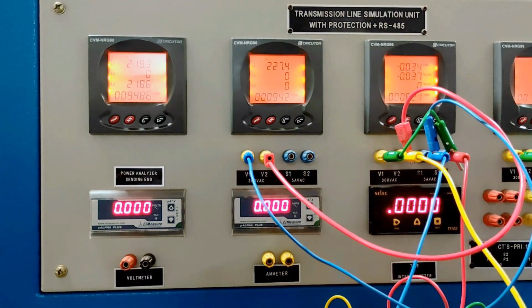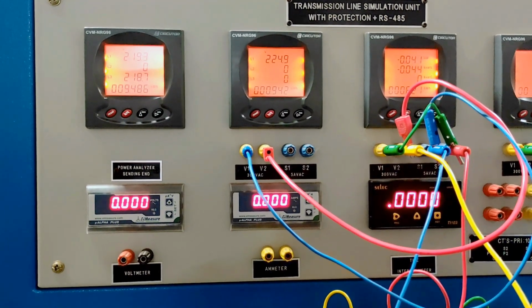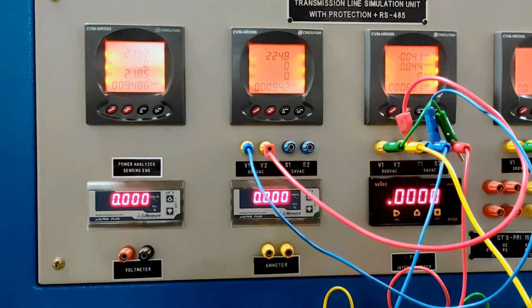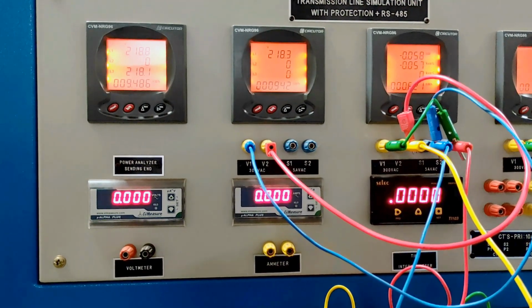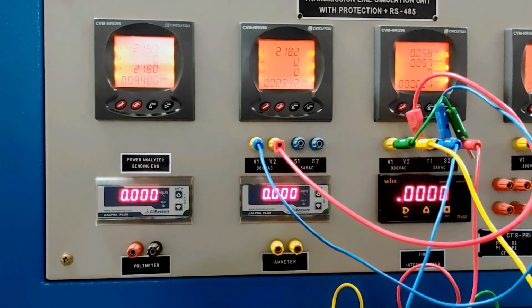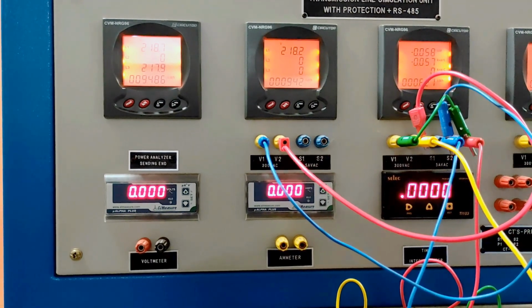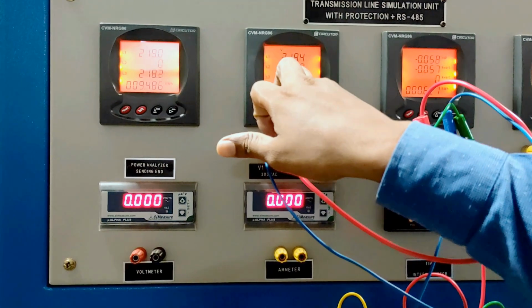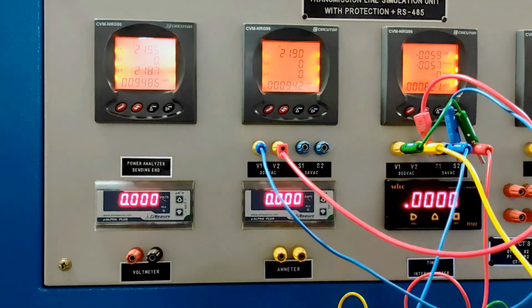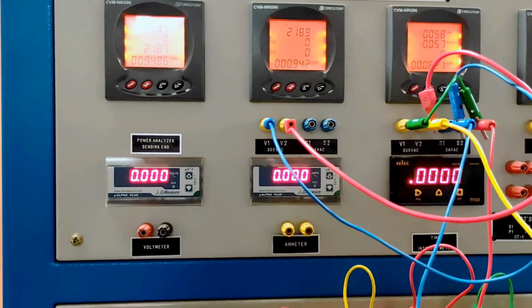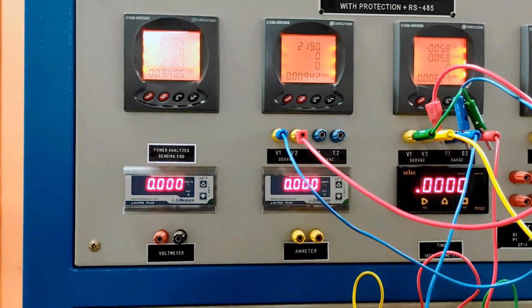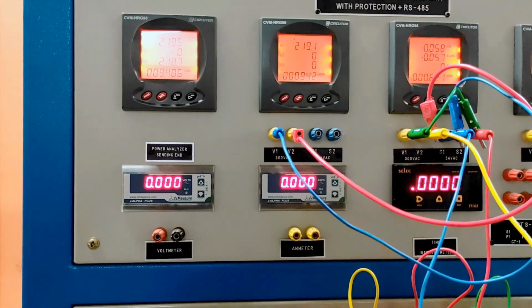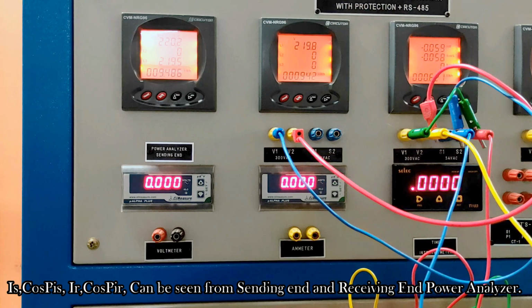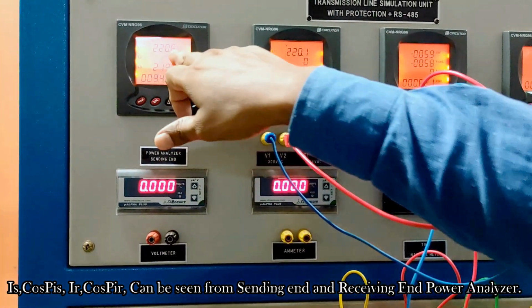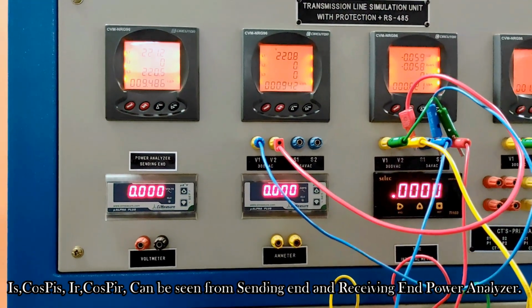So then we have to turn on this once again, 224, again turn on once again. As you can see, the voltage is equal. Right now our sending end voltage is equal to the receiving end voltage, but the sending end is reduced to 219. So by adjusting variac 1, we can increase it a little bit to 220. Okay, so this is 220, this is 220.